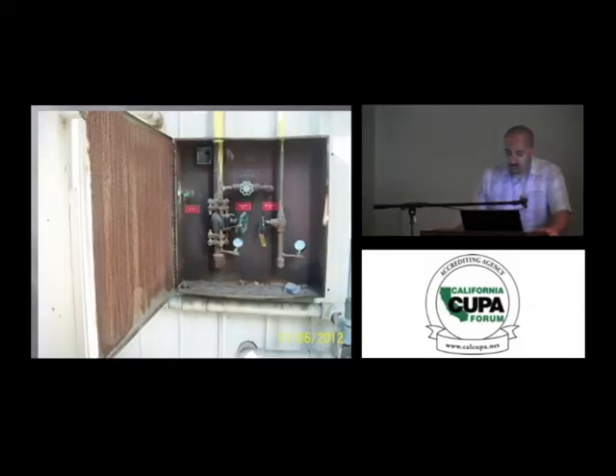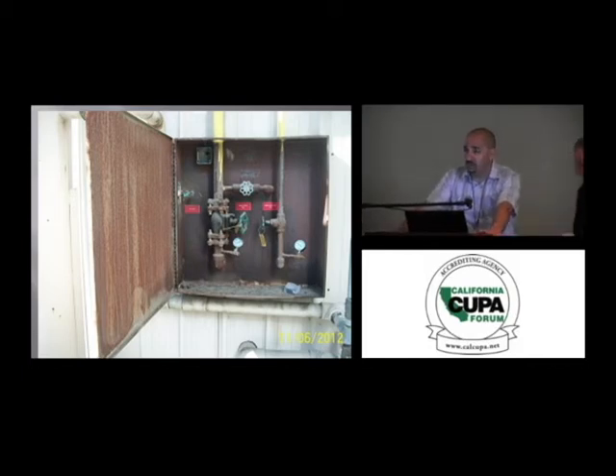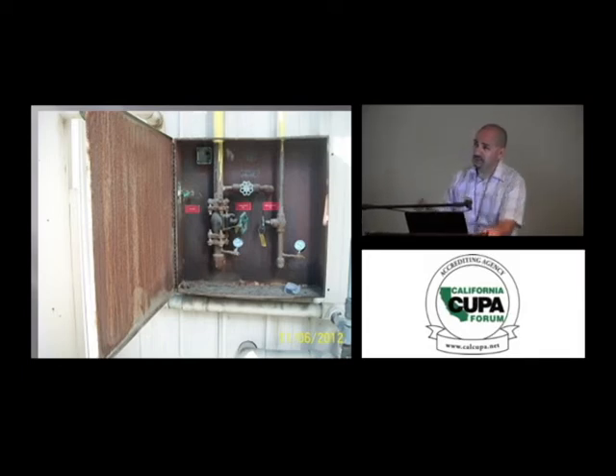This one is the emergency control box. Depending on the year that the facility was built, you needed to install an emergency control box. It needed to be labeled emergency control box up in the front. On the inside, this one is missing the labeling with instructions on how to operate the valves. The valves are labeled valves 1, 2, and 3. This is used also to release and dump all the ammonia out of the system in case of an emergency. Very rarely will this be used, but it's there for a reason.